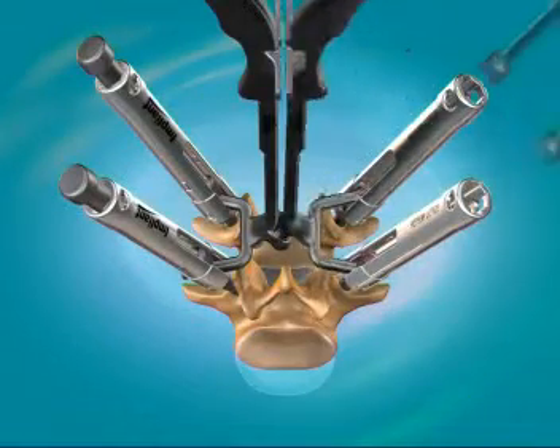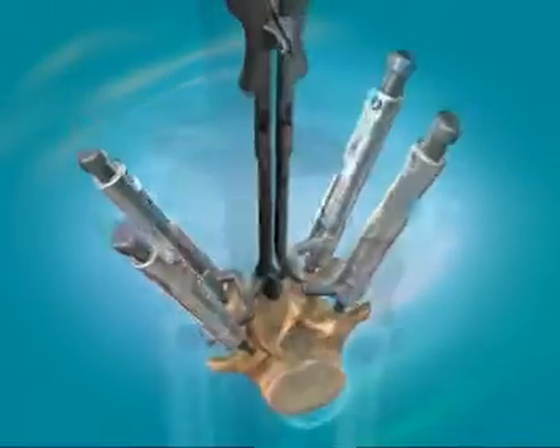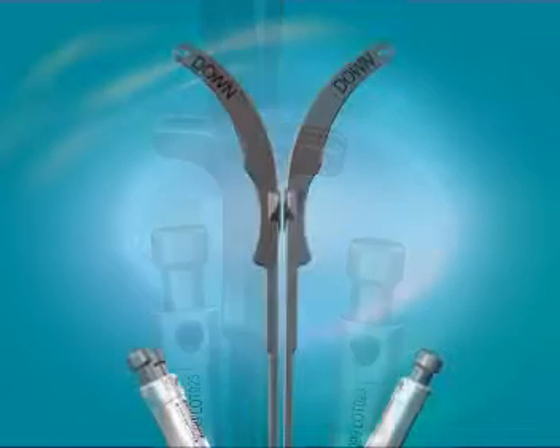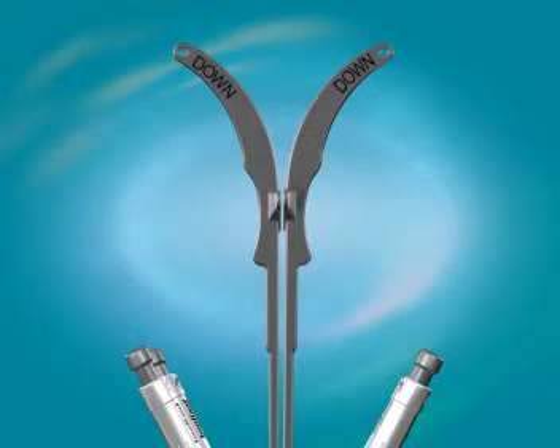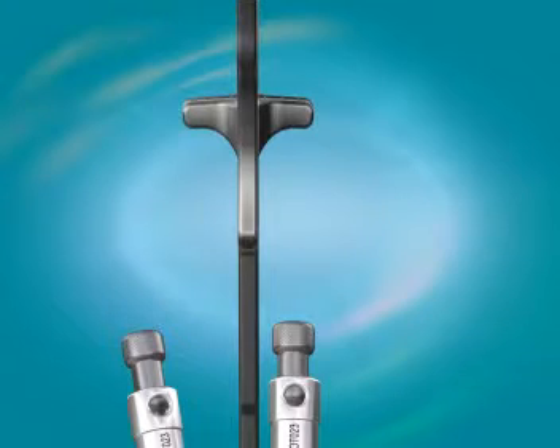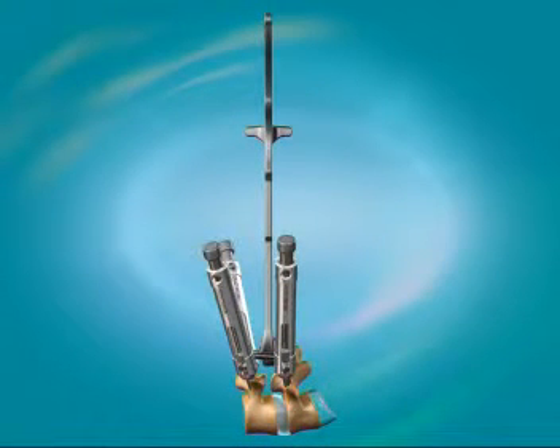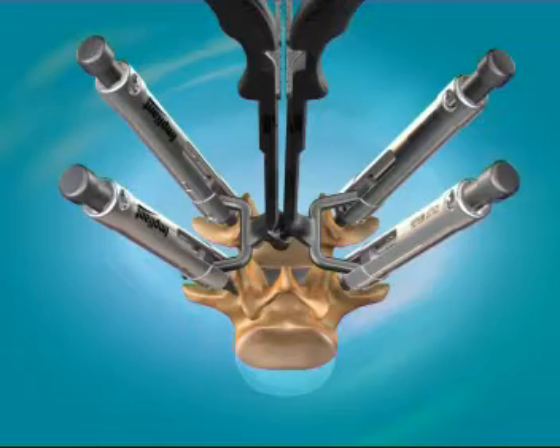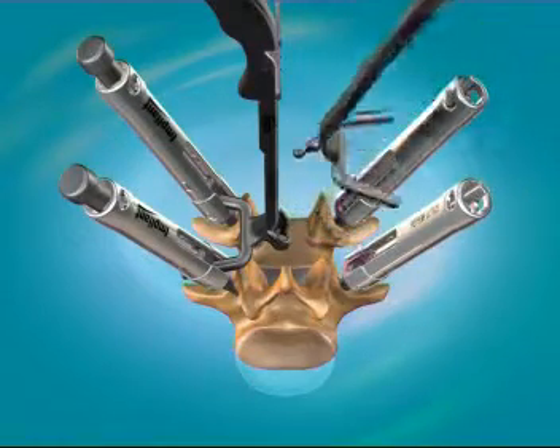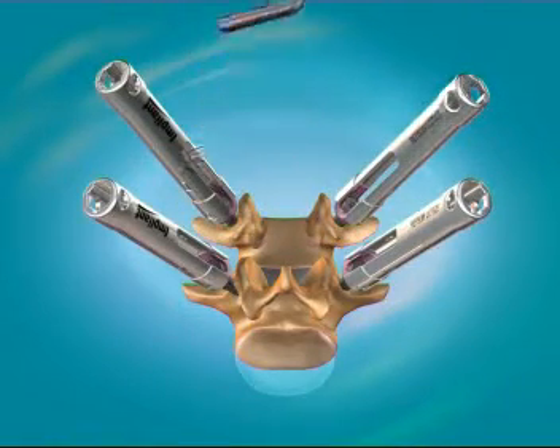When both sides of the gauge are perfectly adjusted, such that the halves are parallel in both planes, this verifies that the pedicle screws are adjusted and that the rod system will properly sit into the pedicle screw heads. Remove all 4 temporary set screws and the gauge.